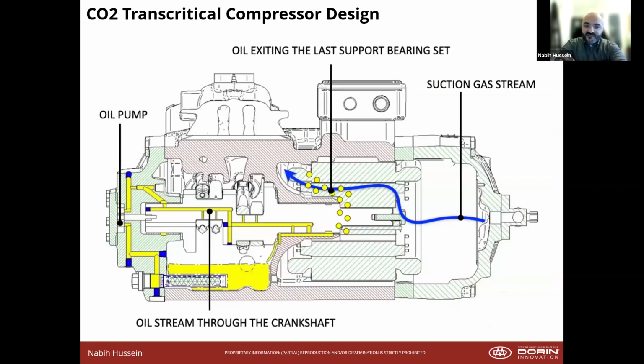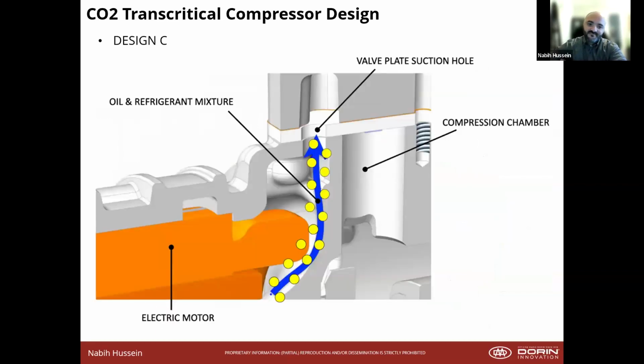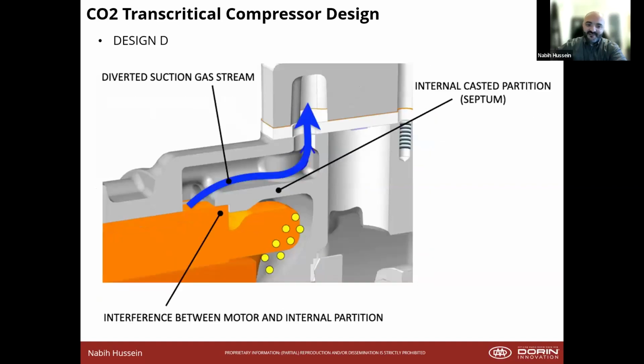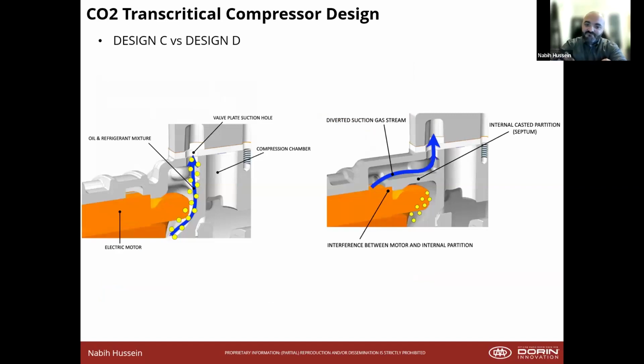Here's a side view of the compressor. You can see suction gas will come in through the suction. It'll cool down that motor, and it will also pick up some oil droplets from the oil that's coming out of the last bearing of the crankshaft. In our previous design, those oil droplets would be pulled into the suction holes of the valve plates. So we added an internal cast partition to stop those oil droplets from being pulled in. Here are the designs side by side. It's not something people would see, but it's the thought that has to go into designing this CO2 compressor to work as efficiently as possible and have the least possible oil carryover.